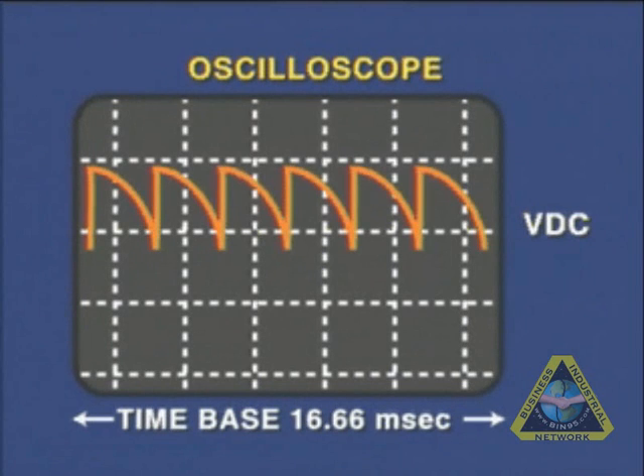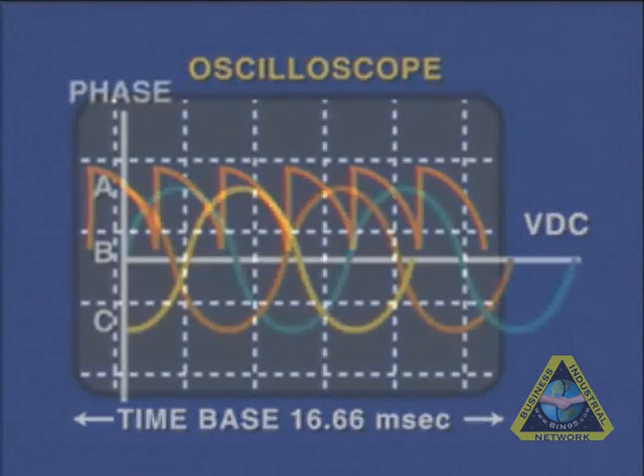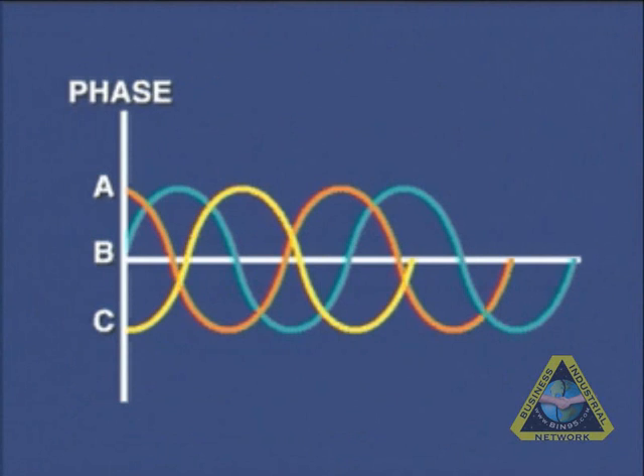You should observe this type of curve, where all six SCR curves should be present within a 16.66 millisecond range which equates to one pulse for each SCR on each half cycle of the three phases. Make sure the scope is set for at least a 16.66 millisecond scale.